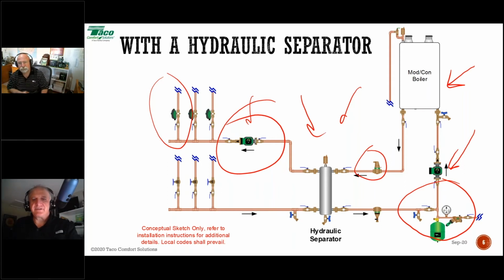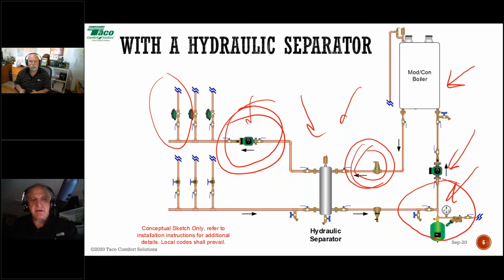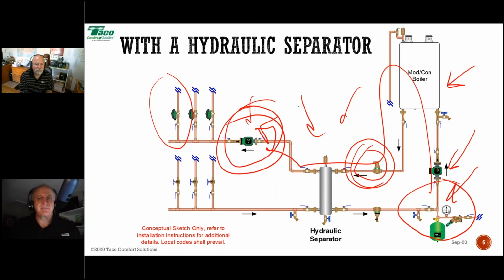So, right. Yeah. This is not the point of no pressure change. This is simply where we put the air separator. What you have here is your point of no pressure change is right here down in the corner. And my system pump is here pumping, pardon my scribbles, away from that point of no pressure change.